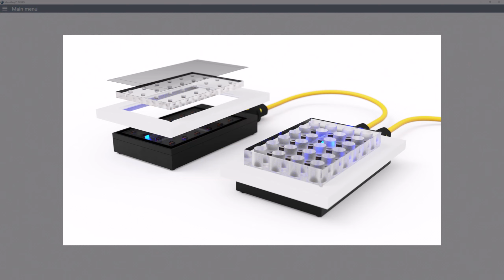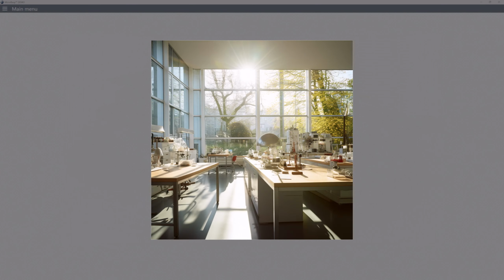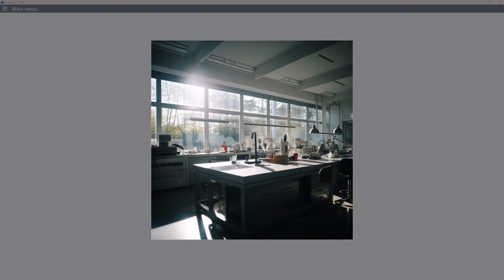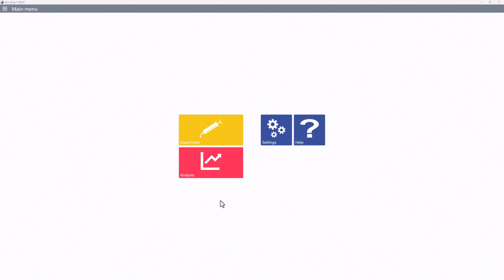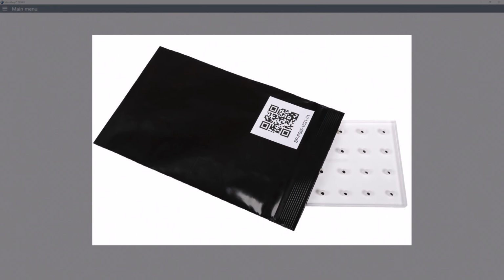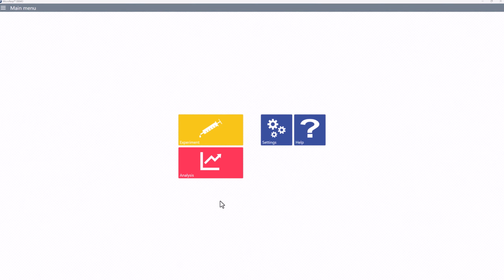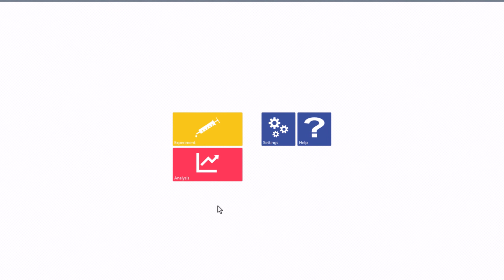The optical oxygen sensor spots used in the microplate system can be sensitive to light sources, especially UV light. So we recommend avoiding exposure of the reader and glass plate to strong sources of light during measurements, as this can interfere with the oxygen readings. It's also why we advise storing the cleaned glass plate in the non-translucent black plastic bag between trials to prevent exposing the sensor spots to light and thus bleaching the sensor dye, causing signal drift.